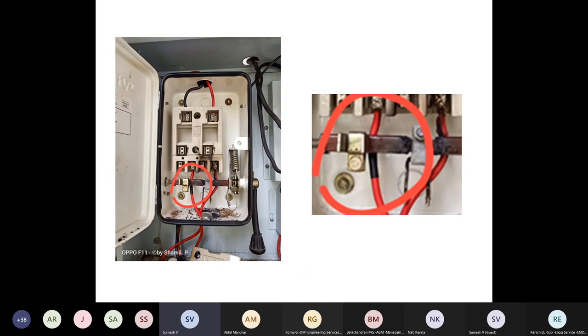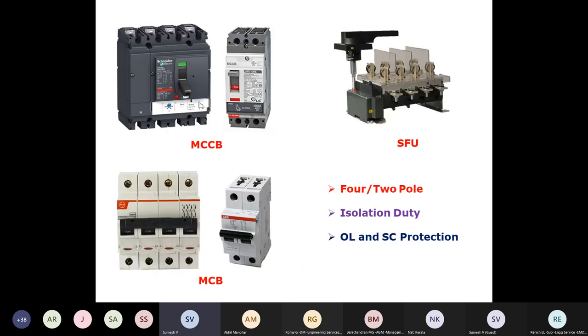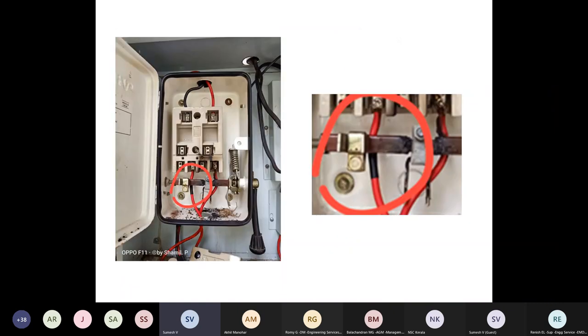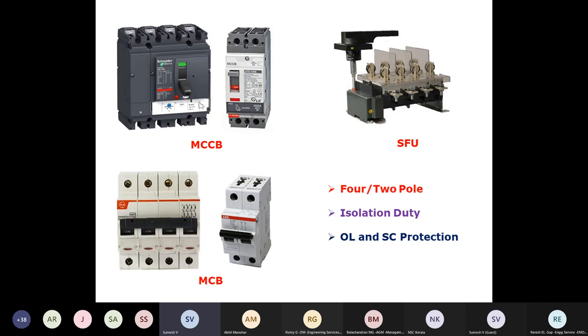This is another photo. What can we do to prevent such accidents? These types of switches are creating problems, so we can very well replace them with an MCB, SFU or MCCB. Only thing is, if three-phase supply is availed, that switch should be four-pole. If it is single-phase, a two-pole switch is to be used. Then that switch should have isolation duty. Also, it should provide overload and short circuit protection to the installation. So MCB or MCCB or SFU will be a better option instead of this type of old switches. By using these equipments, we can ensure protection as well as prevent accidents from damage to these switches.